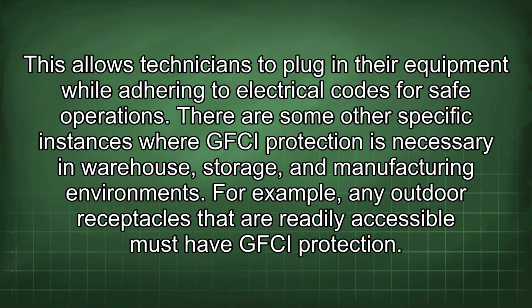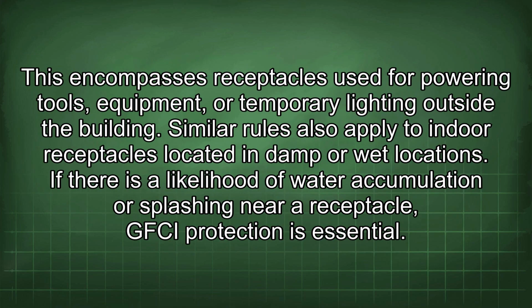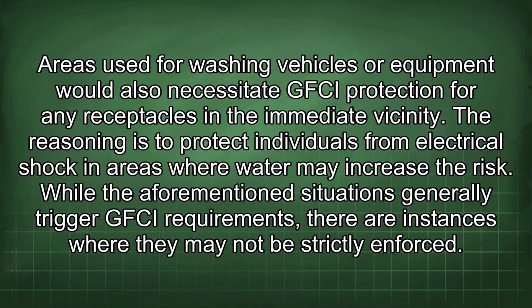For example, any outdoor receptacles that are readily accessible must have GFCI protection. This encompasses receptacles used for powering tools, equipment, or temporary lighting outside the building. Similar rules also apply to indoor receptacles located in damp or wet locations. If there is a likelihood of water accumulation or splashing near a receptacle, GFCI protection is essential. Areas used for washing vehicles or equipment would also necessitate GFCI protection for any receptacles in the immediate vicinity. The reasoning is to protect individuals from electrical shock in areas where water may increase the risk.